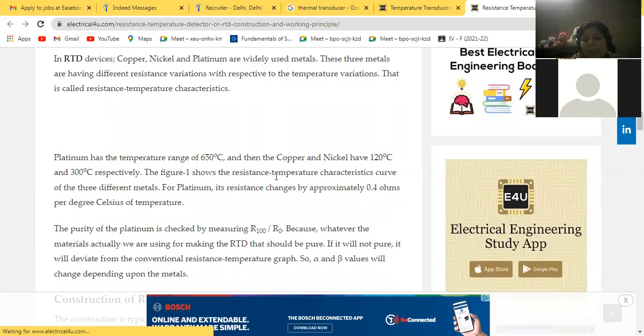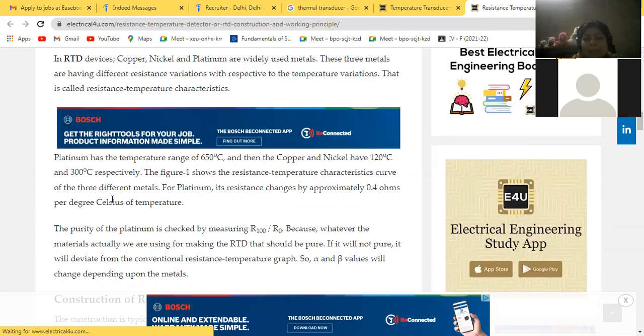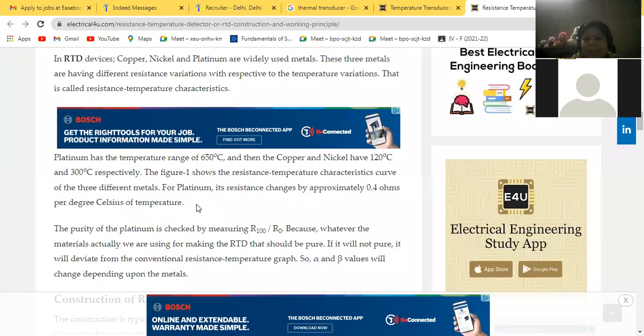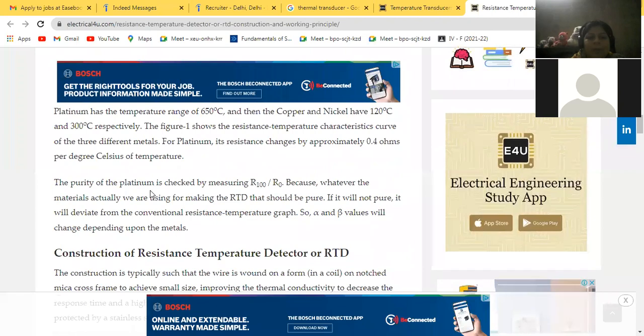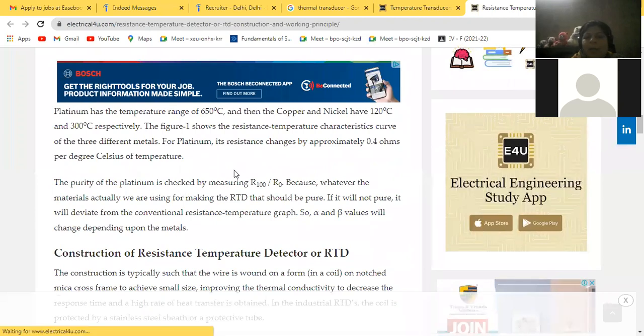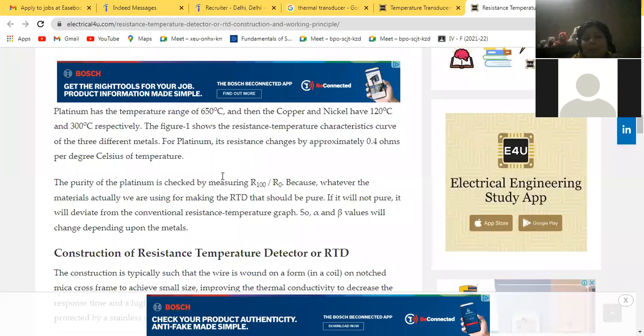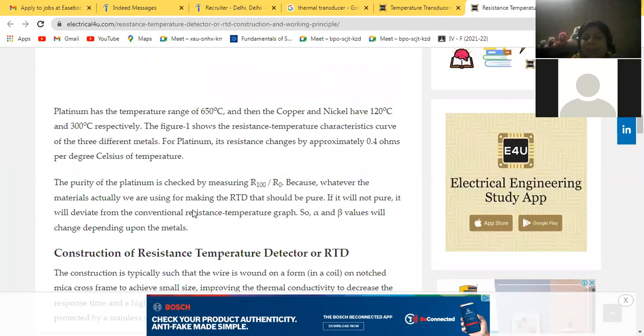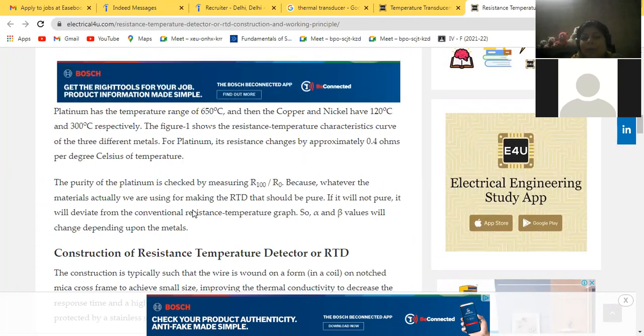Now figure 1 shows the resistance temperature characteristics curve for the three different metals. For platinum, its resistance changes by approximately 0.4 ohms per degree Celsius of temperature. The purity of the platinum is checked by R100 upon R0, because whatever material we are using for making the RTD should be pure. If it is not pure, it will deviate from the conventional resistance temperature graph. So alpha and beta values will change depending upon the metals.